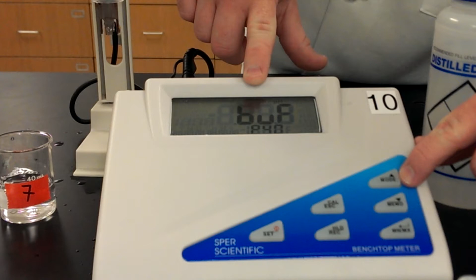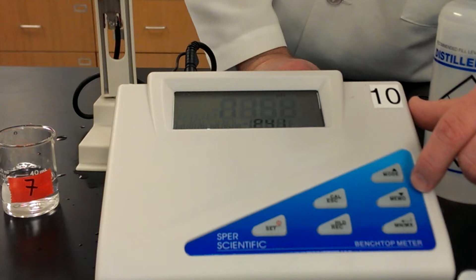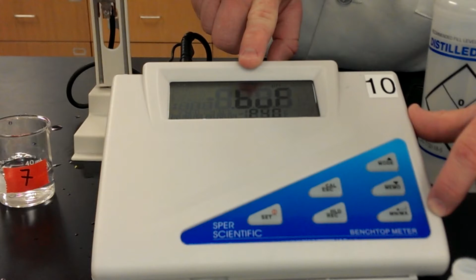It has a little curved arrow on the top part of the button, and it says MN/MX on the bottom part of the button. So we're going to hit that, and there's 2 different settings you can choose. You can choose what it's on now, which is CUST, that's what we want, that's a custom setting, or you can choose NIST, and basically that is just a determination between 2 different types of buffers. We don't have an NIST buffer, so we're going to leave it on the custom mode. So it should say CUST, and after we have that, we're going to push that enter button again, and it should go back to saying BUF.